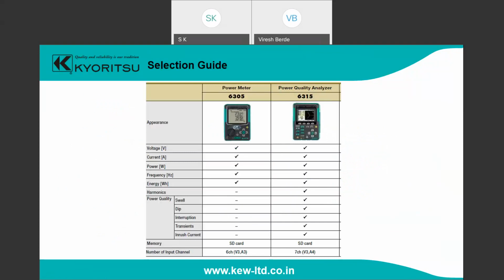Now this is our selection guide. We have two instruments: one is a power meter, model number 6305, and the other is a power quality analyzer, model number 6315. You can see the measurement values. The 6305 is only a power meter, measuring voltage, current, power, and frequency. The 6315 is a power quality analyzer, which also measures harmonics, power quality measurements, dips, interrupts, transients, and inrush current.